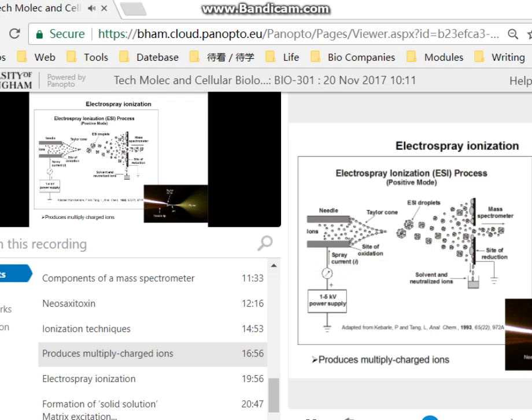This shows the electrospray process. In proteomics, our mixture of peptides is in solution — in a mixture of water and organic solvent, commonly acetonitrile. The peptides are pumped through a capillary, and a voltage is applied between the capillary and the entrance to the mass spectrometer. As a consequence of the interplay between the surface tension of the liquid and the electric field, a Taylor cone forms at the exit of the capillary, and at its tip the solution is unstable and droplets form containing your peptides in water and acetonitrile.